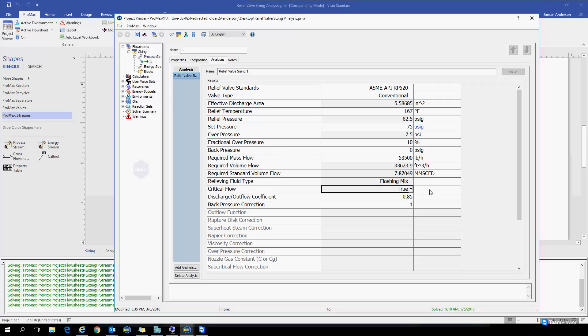PROMAX will also tell you whether this is a critical flow situation. So depending on your relief pressure and your back pressure, PROMAX will calculate whether critical flow will be achieved or not or whether we'll have choked flow in this instance. It's telling us that this is true for our case right now.